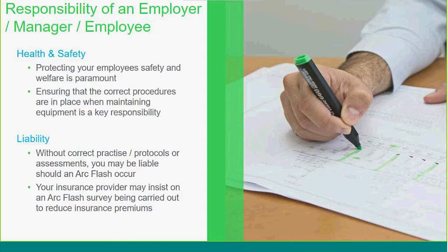There may be a cover off, you may be doing some testing inside the switchgear. That's the point at which you will be exposed to that energy. So the arc flash study gives you a very good indication of the amount of energy that's involved at that point and what mitigation techniques you might want to deploy to remove yourself from that risk.